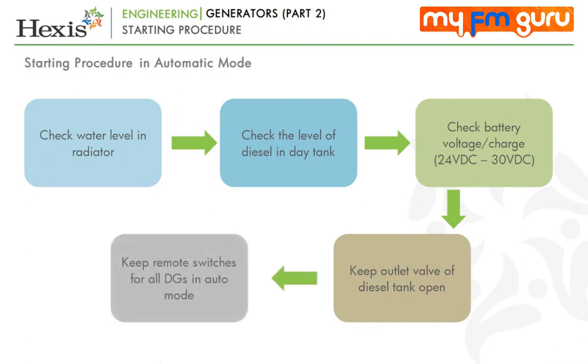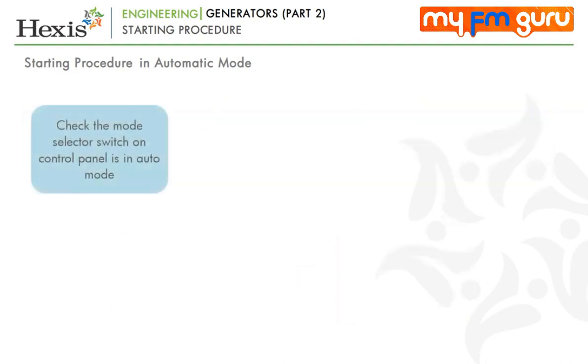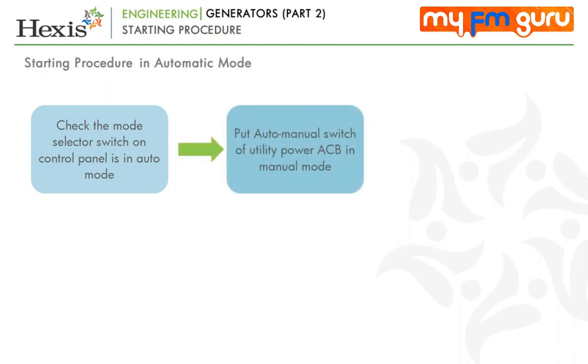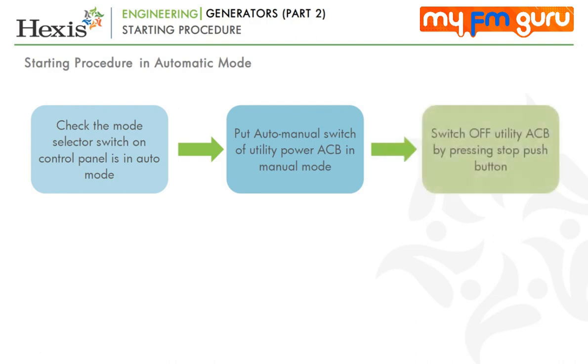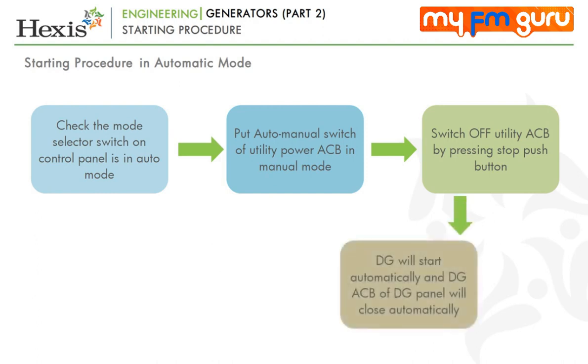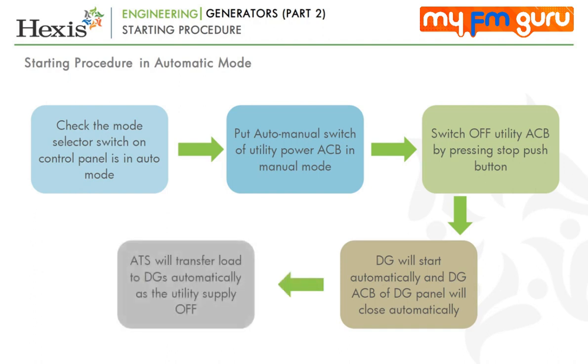Ensure that the remote switches for all DGs are in auto mode. Ensure the mode selector switch on control panel is in auto mode. Put the auto manual switch of utility power ACB in manual mode. Switch off the utility ACB by pressing stop push button. Remember that the DG will start automatically and DG ACB of DG panel will close automatically. Second DG will start automatically and DG ACB of DG panel will close automatically after synchronization. Note that the ATS will transfer load to DGs automatically as the utility supply is off.